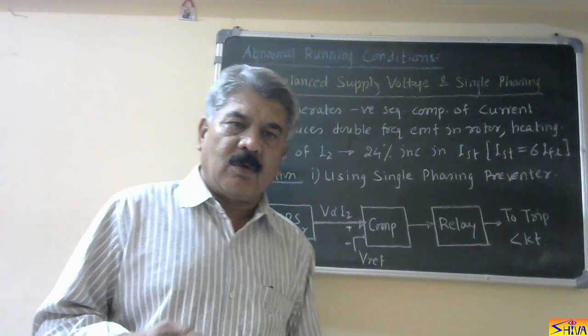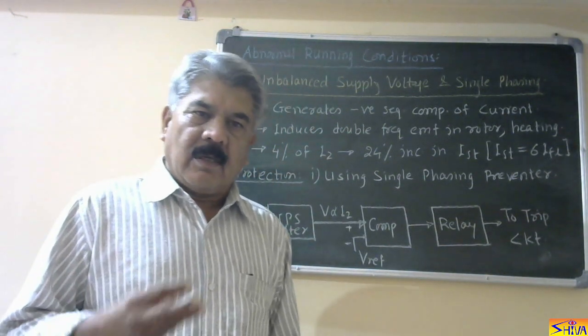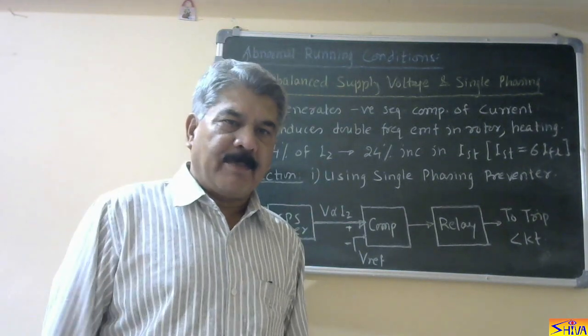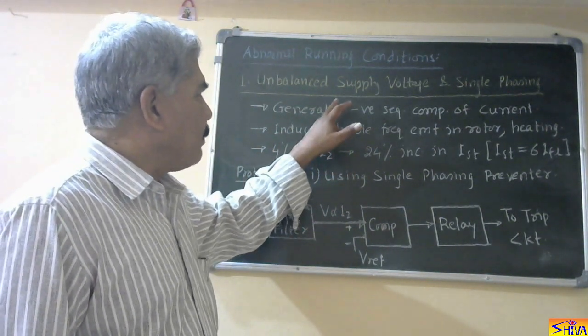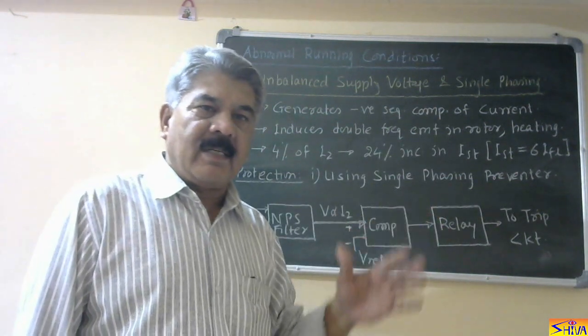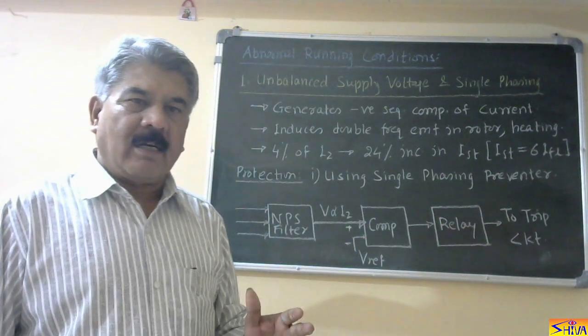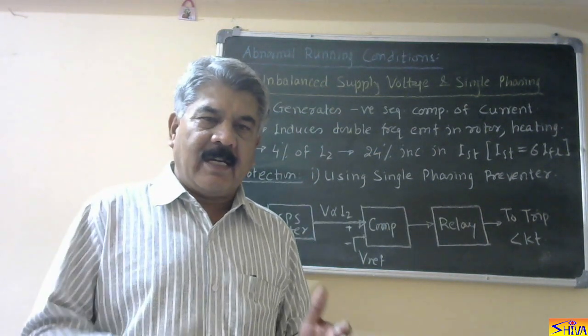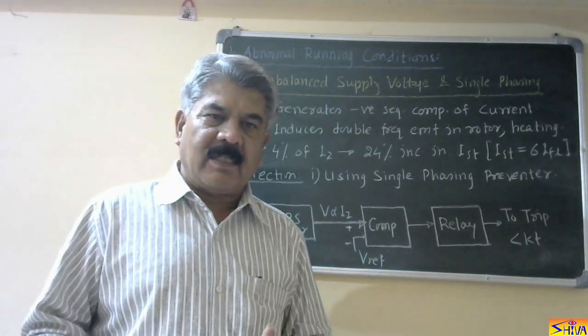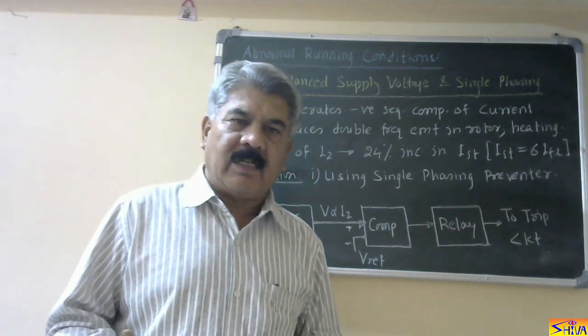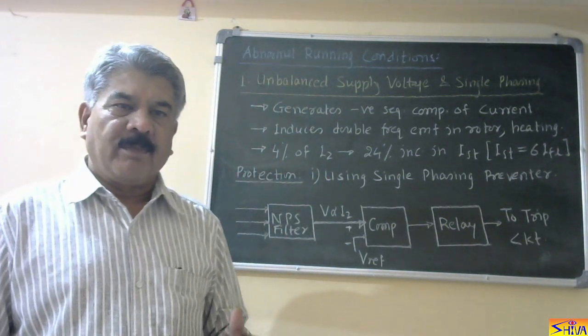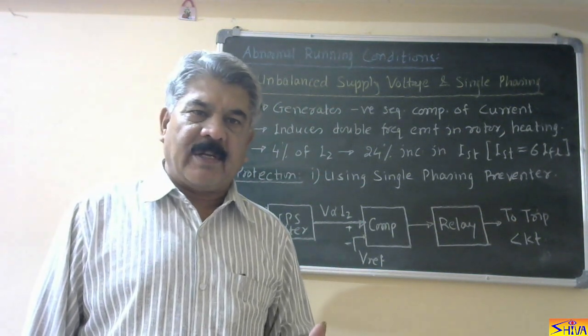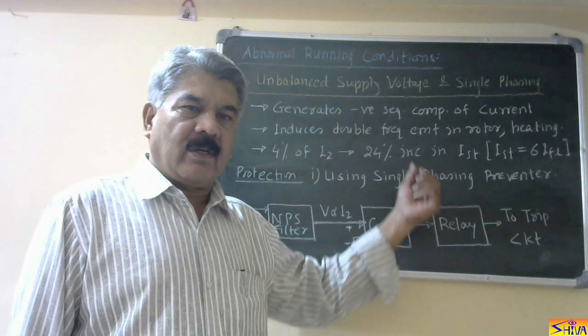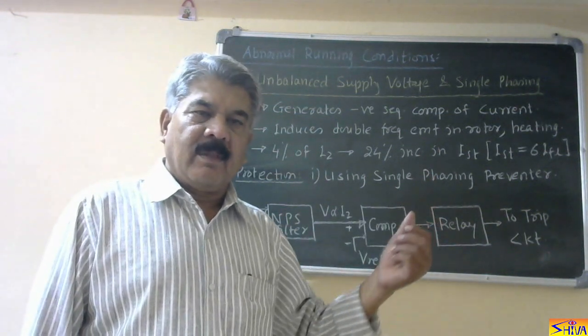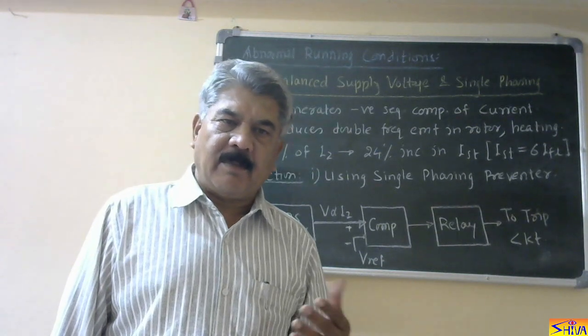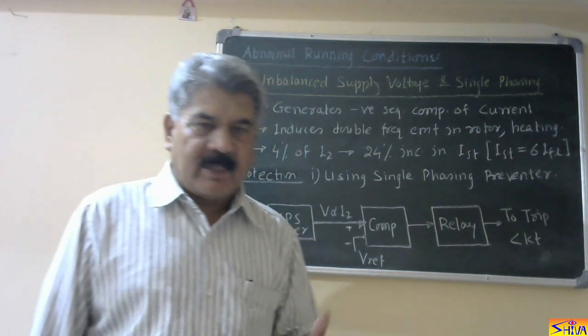When we are using an overload protective device, it may be current sensing or it may be temperature sensing. The effect of this unbalanced supply voltage or single phasing is an increase in current magnitude, and increase in current magnitude causes heating. That heating is detected by the temperature sensing protective device, and the increase in current magnitude is detected by the overload protective device. So if we are providing adequate protection for overload, this condition is always detected by the overload protective device, whether current sensing or temperature sensing.